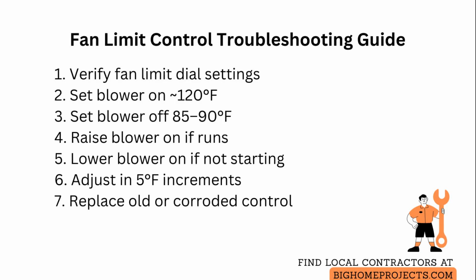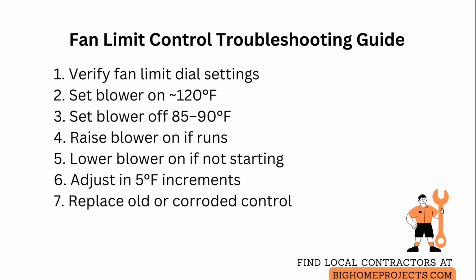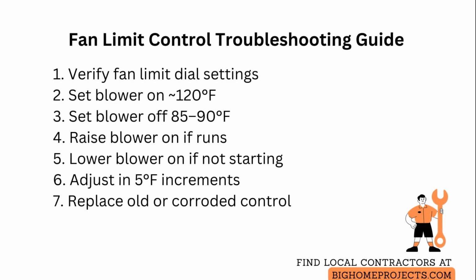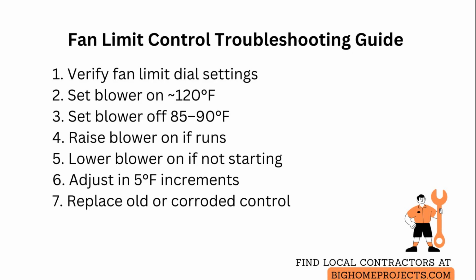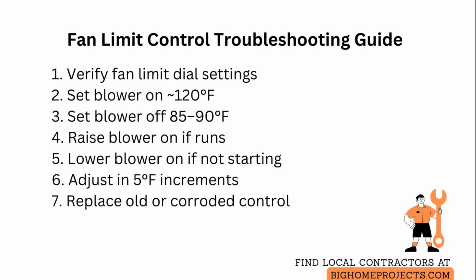If the blower never comes on during warm cycles, lower the blower on setting and confirm the operating thermostat and heat call are functioning. When adjusting, make small changes of 5-degree increments and allow a full heat cycle to complete before further adjustment, so you can observe true behavior.